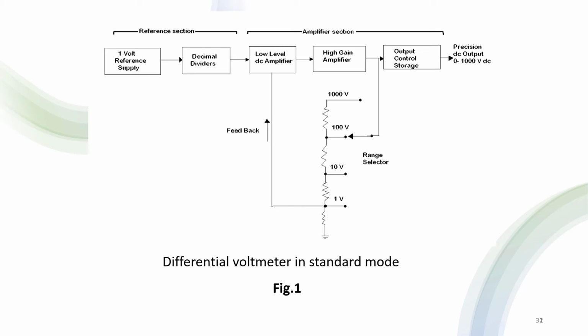This reference output voltage is then applied to a high-gain DC amplifier. In the standard mode of operation, the differential voltmeter is used to provide a standard reference source in the laboratory. This instrument generates DC voltages from 0 to 1000 volts. There are different ranges in which the meter generates. The standard voltages are available in the different ranges as 0 to 1 volt, 0 to 10 volts, 0 to 100 volts and 0 to 1000 volts. Next, one of the modes is the standard mode. The next mode is the differential voltmeter mode.